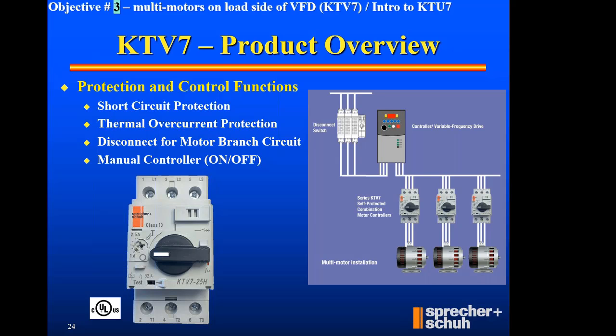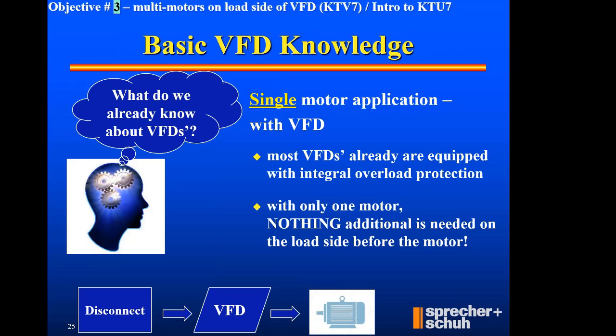And just finishing my point about the illustration, on the illustration there, I see 3 KTVs kind of separated just for the aesthetics of the picture. In actuality, I'm going to have 3 KTVs right next to each other, and I'm going to use bus bar to pass the continuity across all 3. So we've got bus bar available for this, and I'm going to feed it with a supply block. So I only have to feed it 1 time. So that kind of gives a projection of that visual.